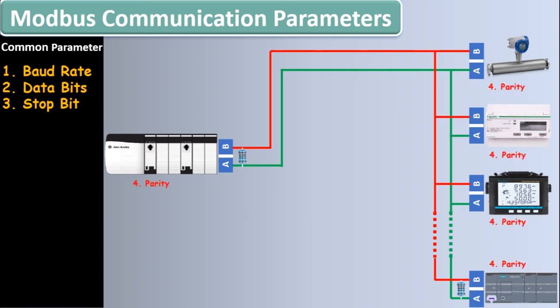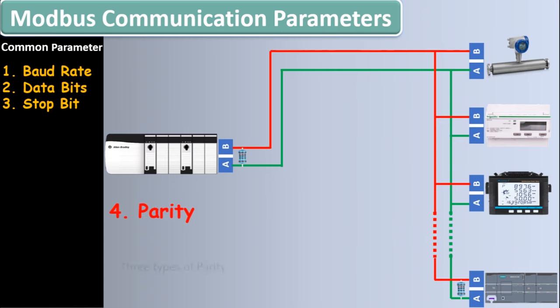The fourth common parameter in RS485 communication is parity. All devices in the same RS485 network must have the same parity. Parity is also a sort of error checking. There are three types of parity: none, odd, or even. Usually none parity is used because the protocol used on RS485 has its own way of checking errors.